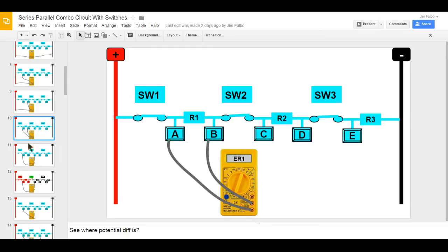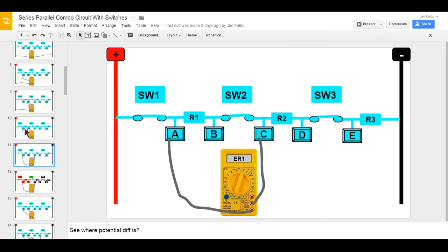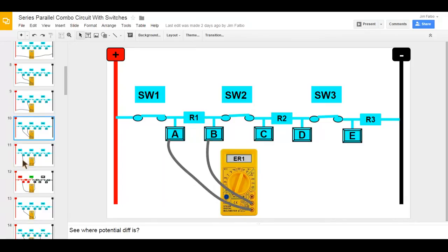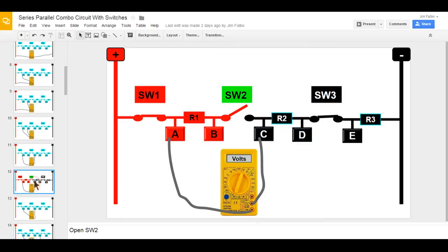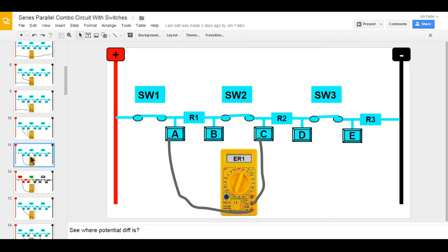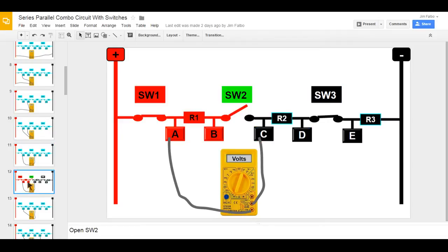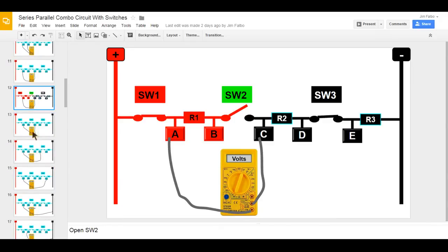Moving the meter lead shows I'm still only reading the first load's voltage drop because a closed switch is just like a piece of wire. When I open switch two, I see full supply voltage. Full voltage is your dead giveaway in a series circuit — if you see full supply voltage across two points, that is where current flow has been stopped.